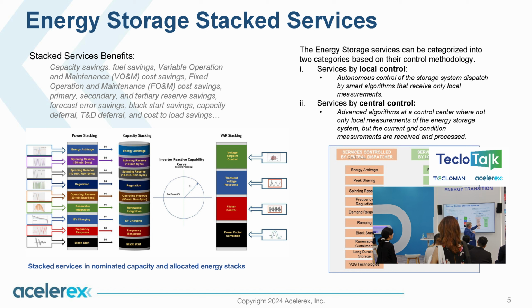Some of the services include voltage support, flicker control, power factor control, virtual inertia, frequency response, and renewables firming. We were told by the National Renewable Energy Lab of the United States that you can integrate as much renewables as you want, and you have nothing to worry about other than the cost. Well, that story's not quite true, because once you get to 20-30%, you start to have reliability issues, and then you have to integrate storage to help with that. So you have to have autonomous local control and grid control, which storage allows, to manage the grid with renewables and distributed resources.